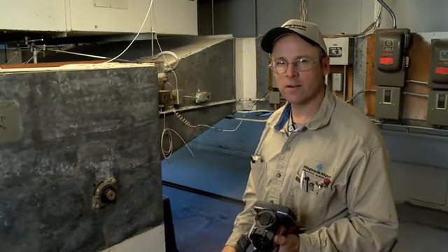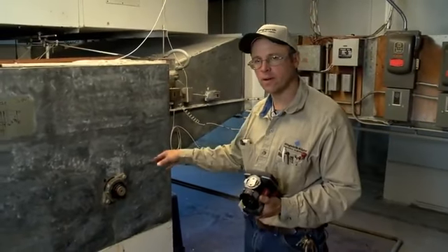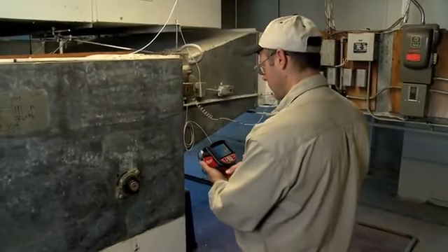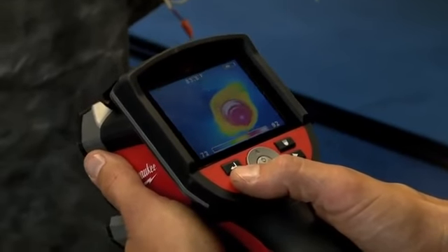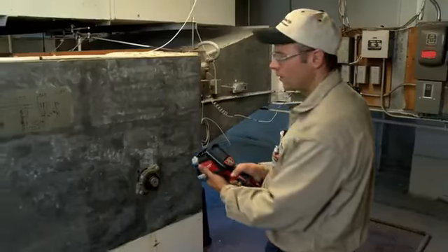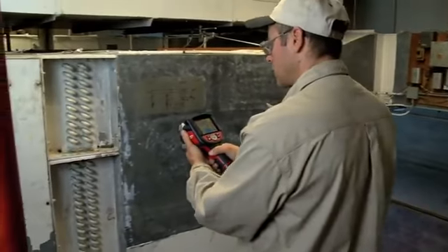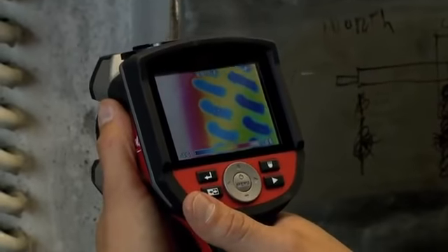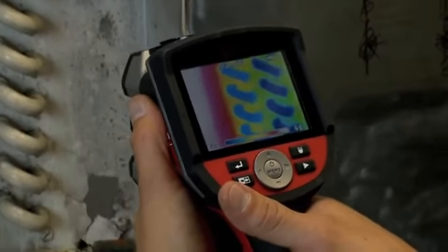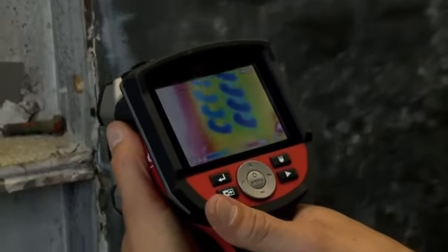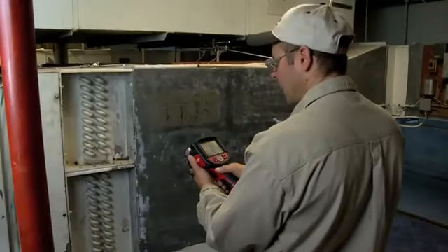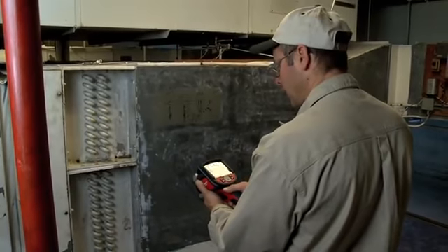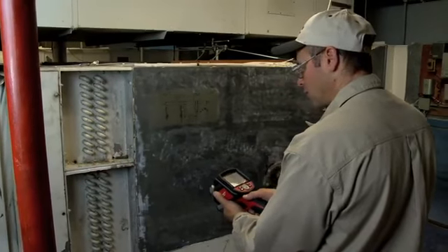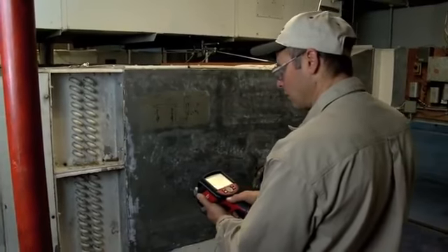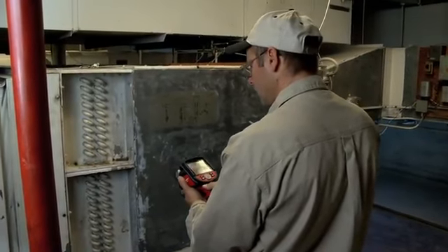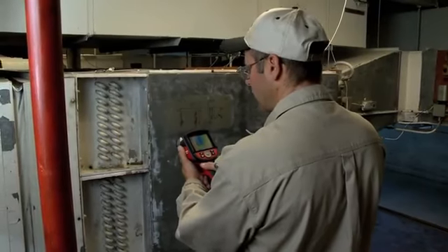On the back side of this air handler, I can get a general overview of this fan bearing and the chilled water coil. In a quick shot, I can see that this fan bearing is running at a normal temperature. I can come over. The nice part about the thermal imaging gun on this chilled water coil, I can see several U-bends at a time, whereas with, say, a digital thermometer or laser thermometer, I'd have to check individual tubes one at a time. Here I can see that all the tubes are running blue, which means cold. It's a great application to have the thermal imaging gun.